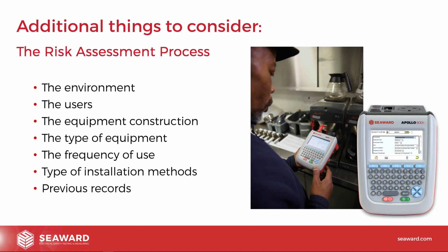Equipment construction. So how is it actually constructed for safety? So is it class 1 equipment where there's an earth needed for its safety, or is it class 2 where the insulation is improved within the construction of the equipment? Generally, as far as the IET code of practice is concerned, class 1 equipment is higher risk than class 2 because it needs that earth. So the need to check that the earth is there obviously means that we need to do that testing a little bit more often to make sure it's there. Whereas with class 2 equipment, generally it's seen as having the safety built in, so the testing of it is not as critical as it would be with, say, class 1.